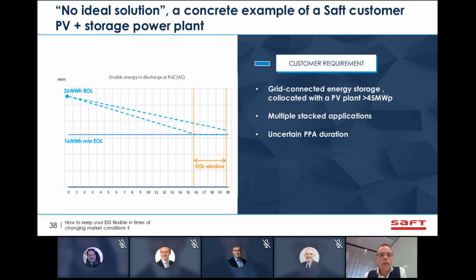Additionally, the PPA itself was not fixed at all, neither its duration, its price and escalation rate, nor the time-shifting power profile itself. So the high-level technical requirements we decided with the customer were pretty open, mainly a beginning-of-life capacity of 26 megawatt hours, a 10 megawatt nominal power, 365 equivalent cycles per year, a usual 97+% availability rate, and a lifetime at the project level of 15 years, but maybe 20 years. This is where we supported our customer in his business case construction by showing 4 main different options and their specific advantages.